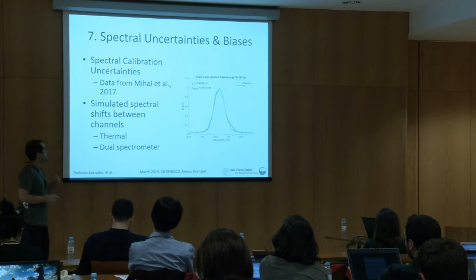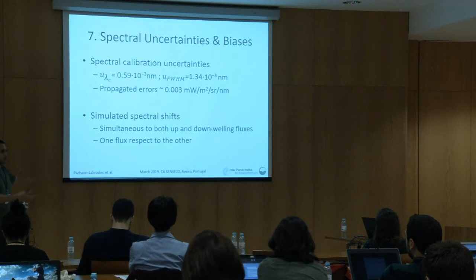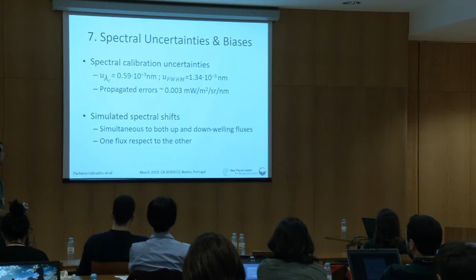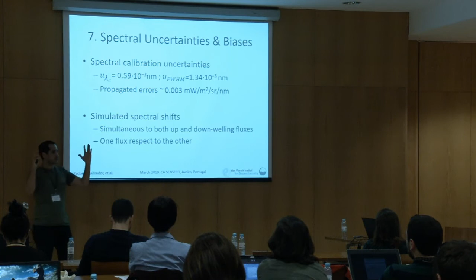But okay, this can happen, maybe because of the fibers, and there are also some other effects that can lead to this kind of thing, and actually we analyzed next changes in temperature, not maybe in the detector, but changes in the temperature in the optical path of this detector. And maybe because of the mechanical expansion of other parts or whatever, you have two different optical paths for each channel, and maybe one of them is shifting with respect to the other. So actually we have an experiment from Carolina, and she was changing the temperature of the body of the spectrometer, and she was measuring some of these lamps, the gas emission lamps.